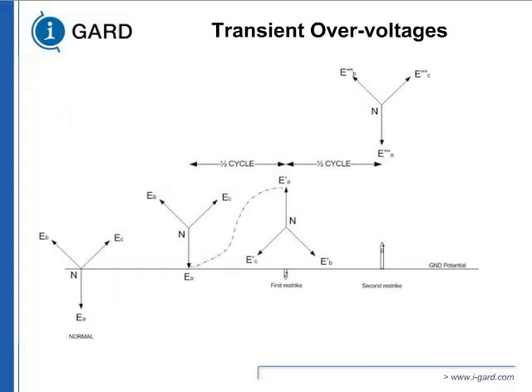You don't have any voltage to the ground; neutral to the ground is going to be very low. If the phase is balanced, you won't have any voltage. As soon as the first fault happens, people believe that phase goes to ground and goes to full voltage. That is not true. The vector arrangement changes. If you see, the neutral is elevated.